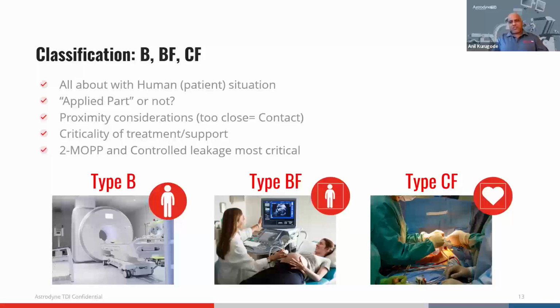Whether it's a surgical procedure or simply a monitoring procedure, as long as the electrical circuit is tied directly to the heart tissue or very close to it, the leakage current requirements are very low, like 1/10 of what is permissible in the BF category. That places enormous burden on the design of power systems, especially when you have a lot of subsystems in play, and all of them have the potential to add leakage current into the product. So we need to be very careful about this category.